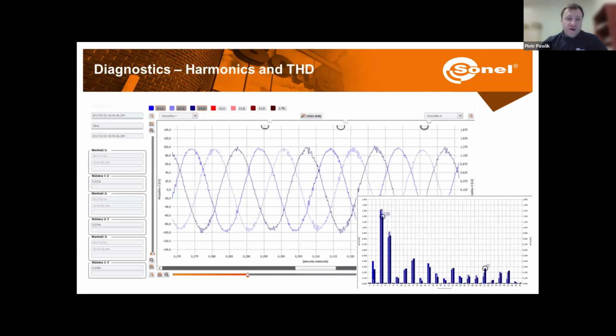So, regarding the impact of the chargers on the main supply, we can check a few different parameters. The first one will be harmonics in current and voltage, together with the THD. So rectifiers, regardless of whether they are in the charging station or in the car, usually generate harmonics by drawing a distorted current. As you can see here in the picture, it is not a nice sine wave; it is distorted, and these are the harmonics.